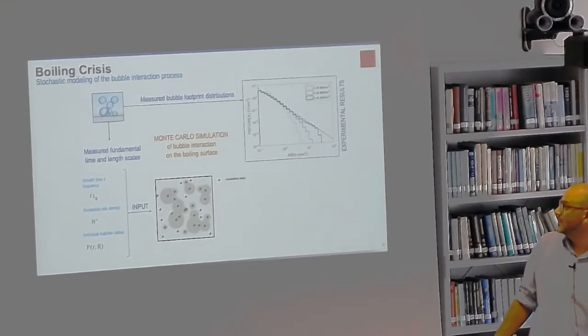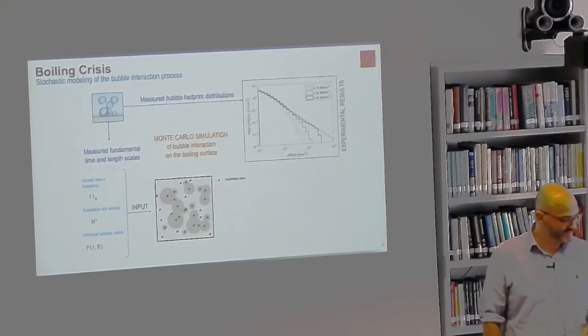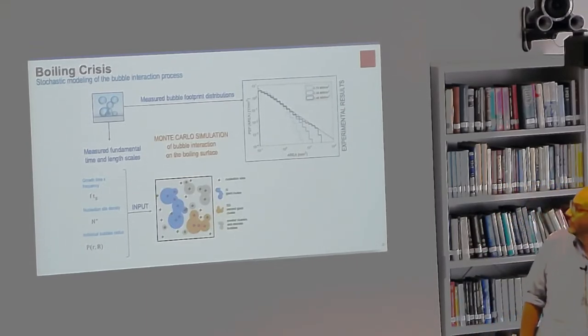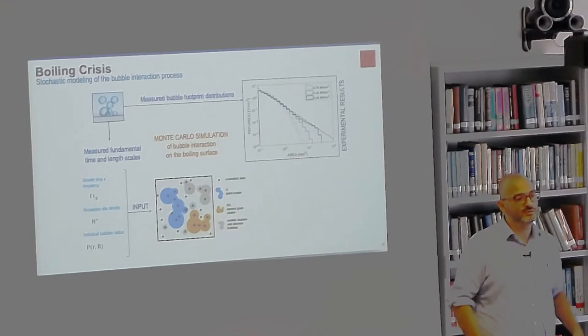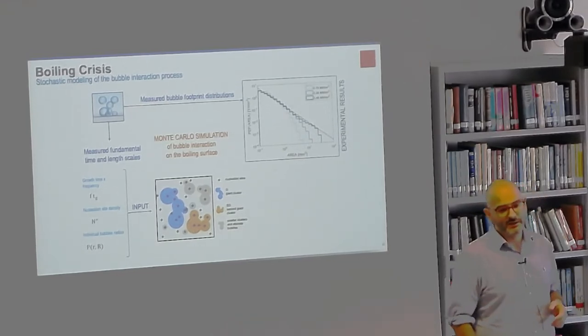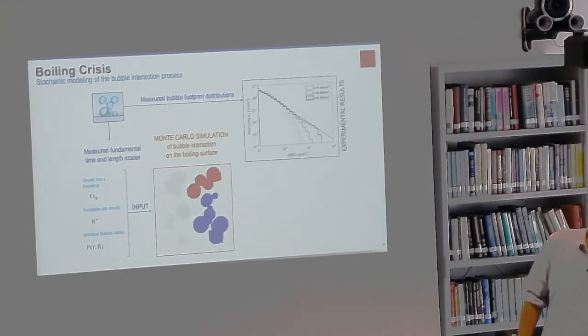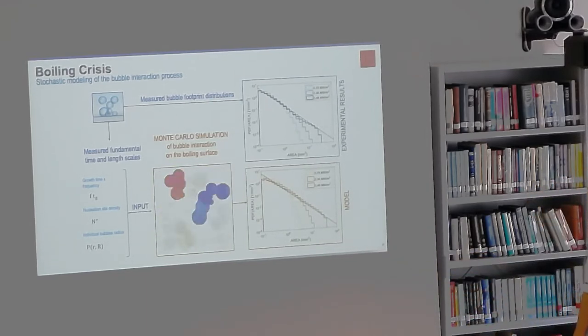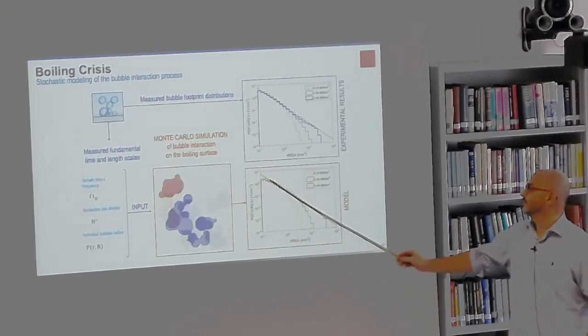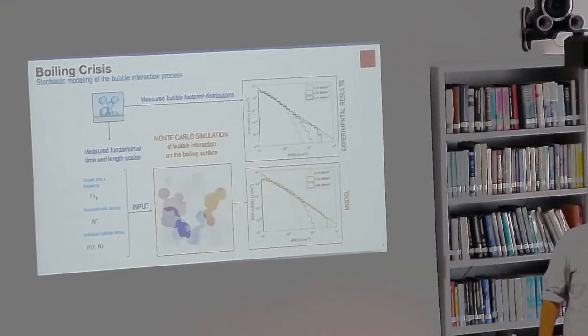You continue this process over and over through all the sites to finish one iteration, then repeat hundreds and thousands of times until statistical convergence. One thing to track is the size of the largest and second-largest bubble cluster — the size of the vapor patches on the surface. Eventually you come up with results very similar to what our experiments reveal, and particularly that at the moment we trigger boiling crisis, this distribution has a power law very similar to what we measure experimentally.